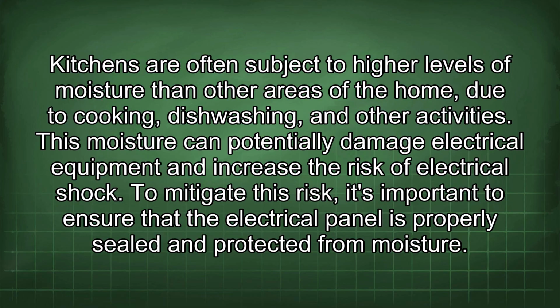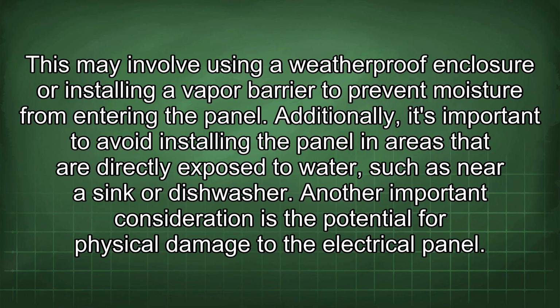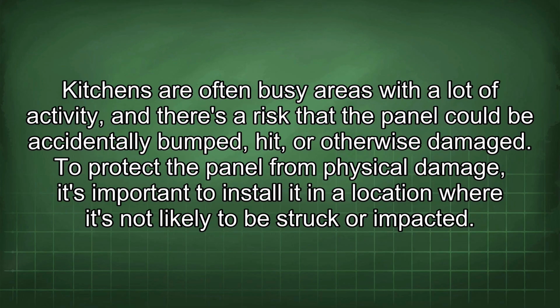To mitigate this risk, it's important to ensure that the electrical panel is properly sealed and protected from moisture. This may involve using a weatherproof enclosure or installing a vapor barrier to prevent moisture from entering the panel. Additionally, it's important to avoid installing the panel in areas that are directly exposed to water, such as near a sink or dishwasher. Another important consideration is the potential for physical damage to the electrical panel. Kitchens are often busy areas with a lot of activity, and there's a risk that the panel could be accidentally bumped, hit, or otherwise damaged.